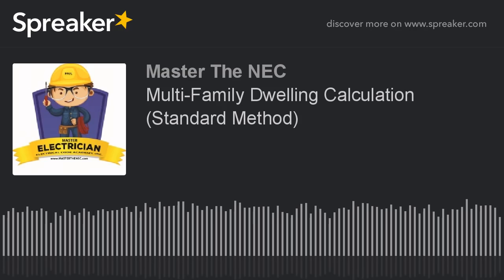Under the air handlers, which each unit has an air handler, it was 21,168. And we took the largest motor of this whole calculation and did it at an additional 25%. So the only real motor here was the air handler. So we took that air handler, 9.8 times 120 times 25%, which is 294. So I add all these up, and I should have 279,912 VA. Okay, that is my service load. And that is the actual calculated load at this point.